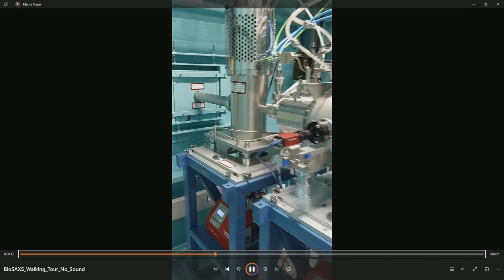That's lots of safety equipment there. So that one at the end there with the corrugated stuff, that's a safety shutter. That is a one-time device. If we detect that there's a person somewhere where they shouldn't be, that thing moves a gate down very quickly, very forcefully. It'll stop the X-rays coming through and save the person, but it is a one-time operation device and very expensive to replace.